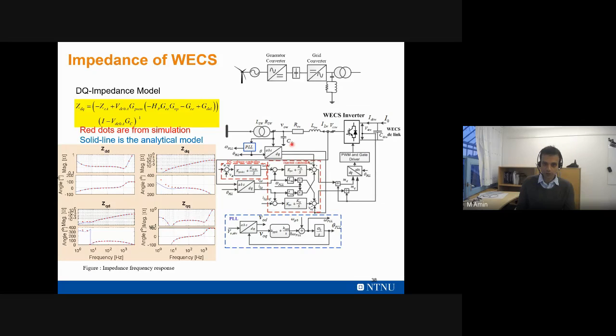We inject different frequency signals at this terminal and let them enter the converter. Since these are different frequency current signals with a low magnitude, around 5% of the operating point, this current also produces the same voltage signal. This voltage divided by the current gives us the impedance.